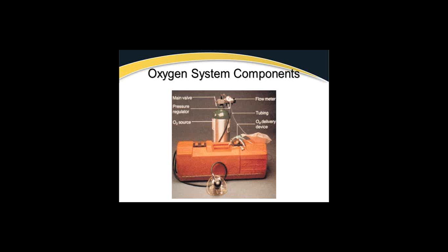The good thing about oxygen is that oxygen alone is not flammable, but oxygen enhances burning. So we can have an open flame in the presence of oxygen, and it's not going to explode. But if there's a fuel source, such as an oily nasal cannula on a patient's face, now you have the heat and the fuel and the oxygen, and it is going to burn. So it's not flammable, but it enhances burning.